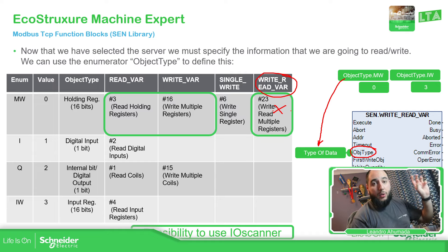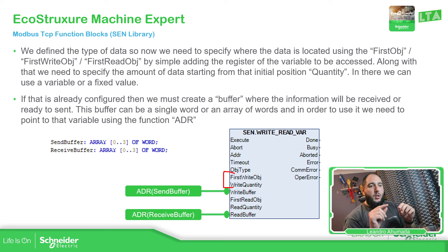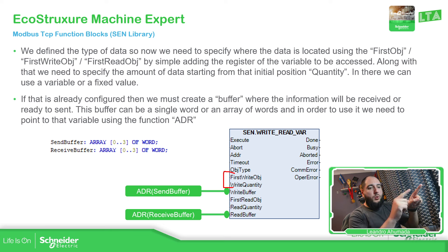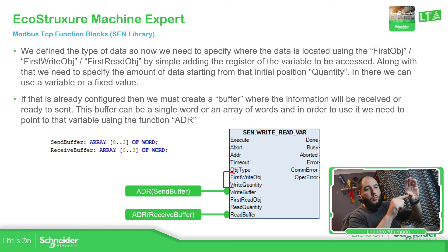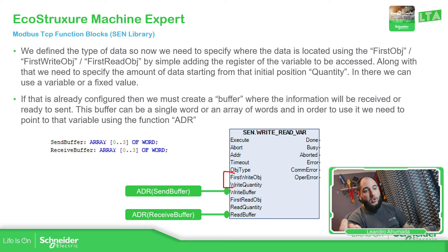We need to define the data that we're going to read and write. First, we need to specify on the device which area you're going to read and write — so we need to define the first object, or first write or first read object, and then the quantity that we want to read and write, so the PLC knows where to look. In these two parameters, we just need to put the address of the device and the amount. If you only want to read one register, just put the number one and the position.